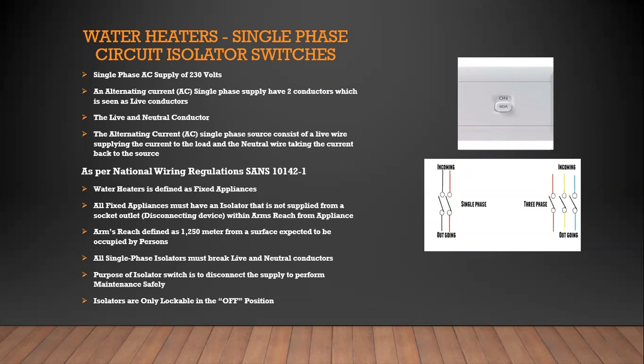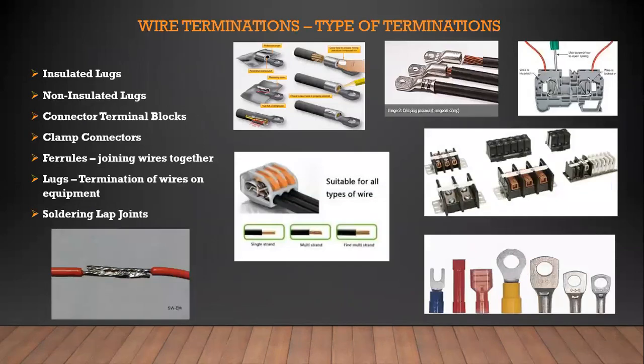I'll also go into the wiring regulations of where the isolator must be installed on a water heater, what it is supposed to do, and how to lock it out or switch it off to work safely. We're looking at wiring terminations, what's the correct type or method to join wires. Can we solder it? Can we use proper connectors? I address acceptable connectors in the industry, such as proper clamp connectors. I use screw type connectors, the choc blocks like we all know them, and how to crimp lugs and ferrules, how to terminate these wires correctly.